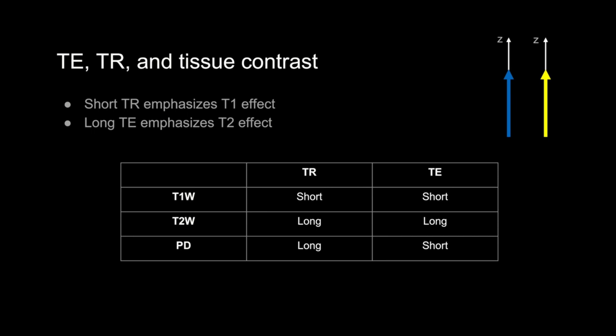A T1-weighted sequence uses short TRs to emphasize T1 effect and short TEs to minimize any T2 effect. T2-weighted images use a long TR to minimize T1 effect and a long TE to maximize T2 effect. Proton density sequences — not used much in routine body imaging — use a long TR to minimize T1 effect and a short TE to minimize T2 effect. If you minimize both T1 and T2 effects, you're left with just the density of protons — hence proton density.